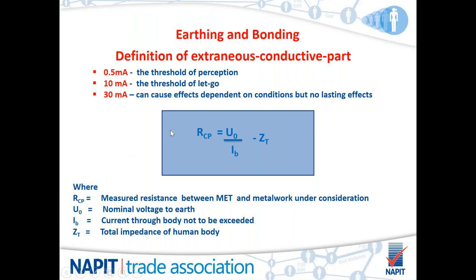We have an equation in the centre, and as you can see, we've got RCP there. RCP is the measured resistance between the main earthing terminal and the metalwork you need to take into consideration. So this is the resistance being a long lead test between the MET and the piece of metalwork you are trying to assess. The next bit is simply the Ohm's law calculation again in reg speak. UO is the nominal voltage to earth of 230 volts, obviously. IB is the current that we don't want to exceed going through the human body. And ZT, impedance, is the total impedance of the human body.